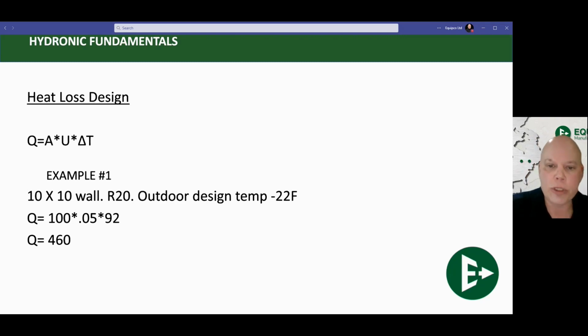Multiply that by 92, which is our temperature differential between 70 degrees inside minus minus 22 degrees outside. And then you do the math. 100 times 0.05 times 92. So you have a heat loss design for that one 10 by 10 wall of 460. That means that through that wall, you will lose 460 BTUs per hour. If you had a room where you had these 4 walls and you did all of them, your heat load for the one room was, let's just say it was 1500.